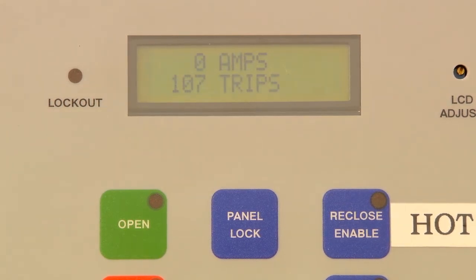Starting from the default menu, pressing the Settings button will show the settings programmed into this control. This particular unit has been programmed for 300 amps. Scrolling down again will display the curve for the fast curve, in this case an A curve. The time dial for that would also be an A curve. The second curve, or the slow operation displayed here, is a B curve, along with a B time dial. You can see this unit is built to withstand up to 6,000 amps. Beyond this point is advanced programming.